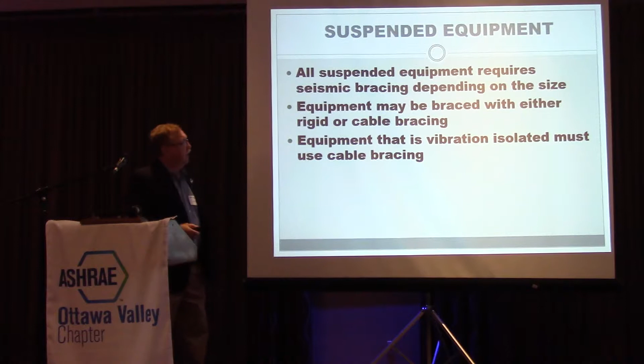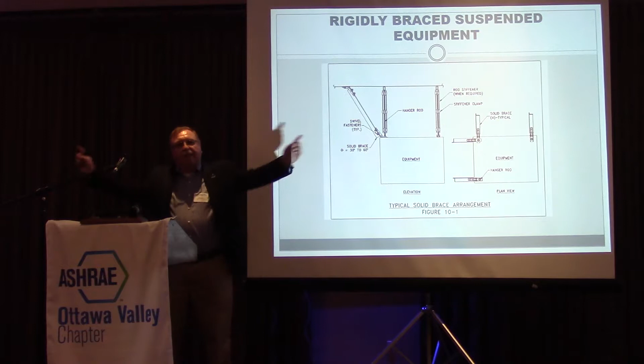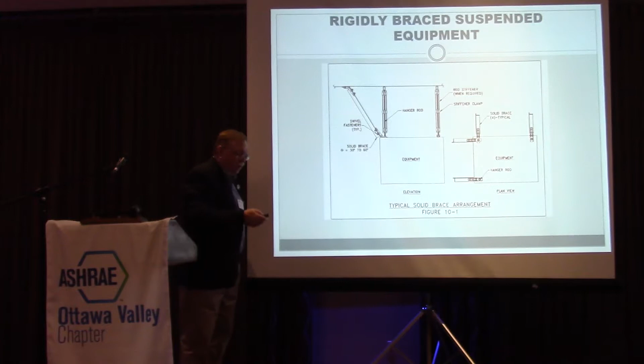So the only thing that's different is, if I do a rigid brace, everything else we did with a rigid brace, be it the ductwork or the piping, had one brace. Can't do that with a piece of equipment, right? The reason we can do it with one brace on duct or mechanical piping is it's got length to it to keep it from being turned. You don't have that with a piece of mechanical equipment. You throw a fan up in the air, put one brace on it, and that thing's just going to spin around that one brace like a top, going in circles. Even 2 braces isn't going to help you. It turns out you need 4 braces. So whether you go with cable systems or a rigid brace, you're going to need 4 attachments for any piece of suspended equipment.